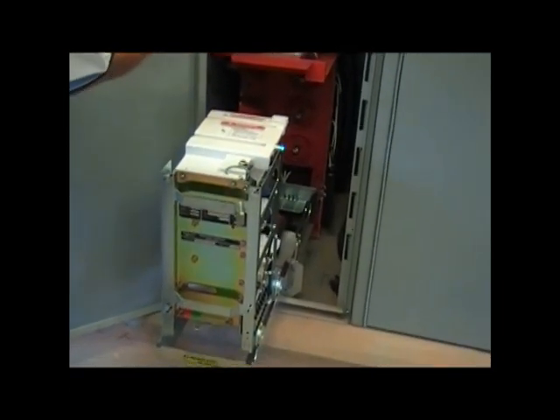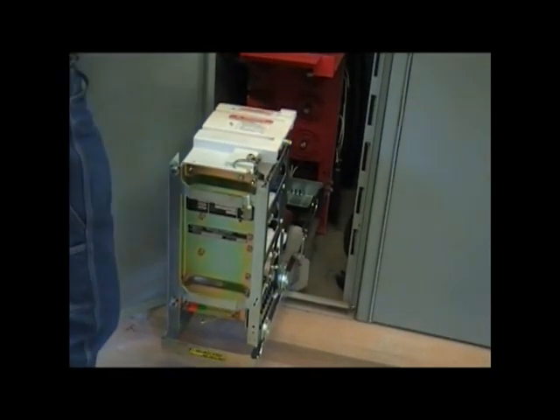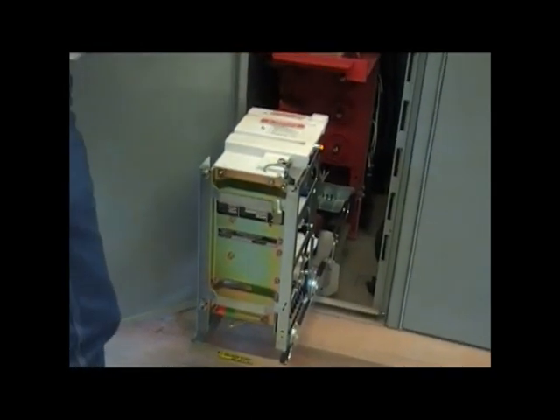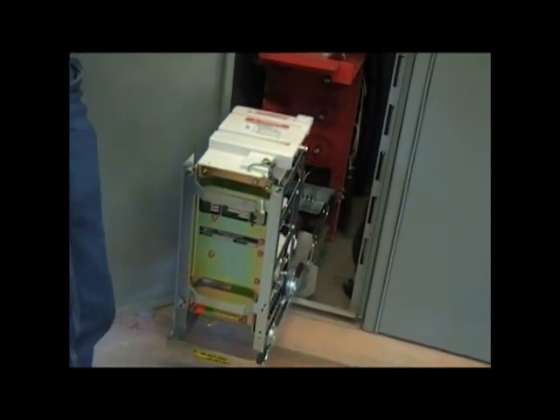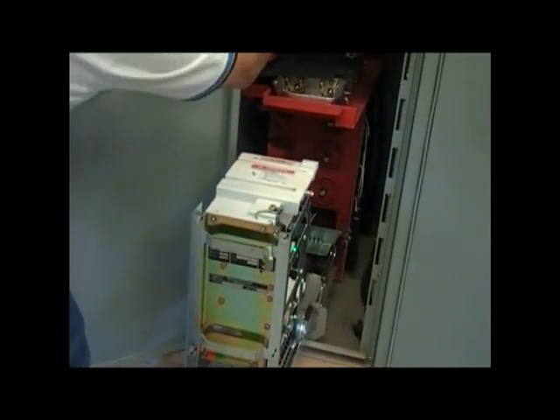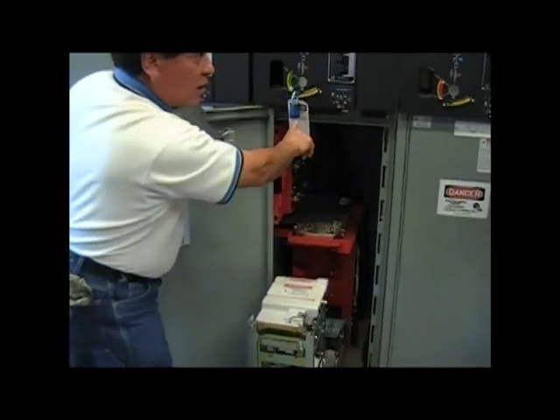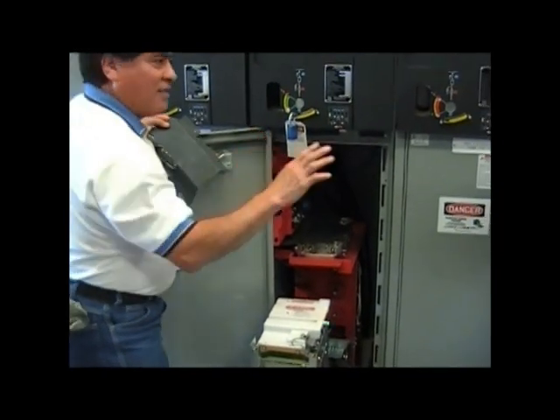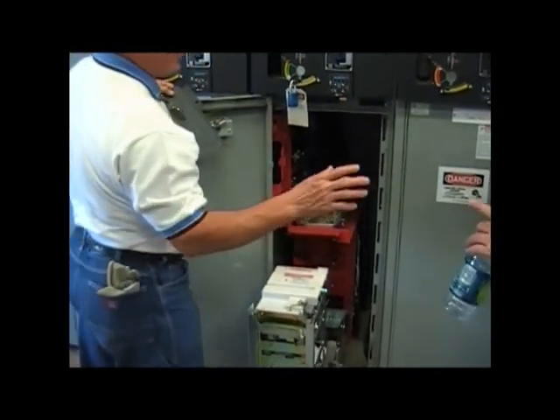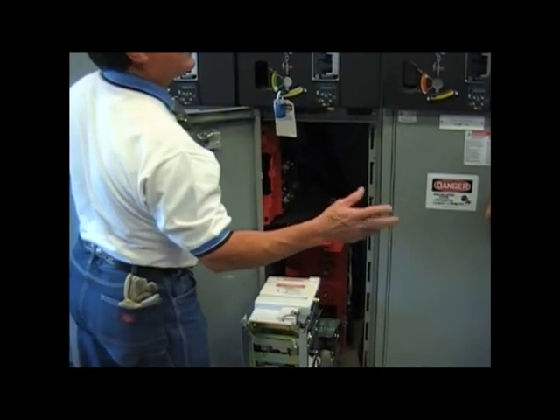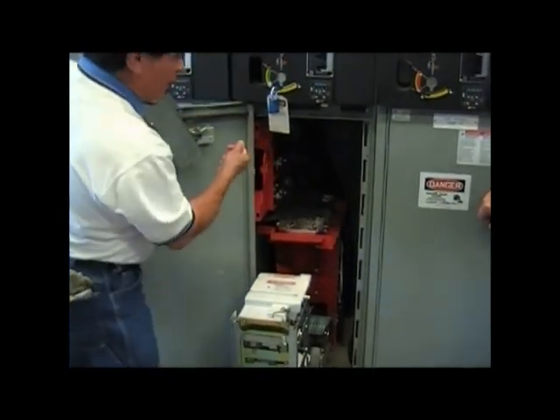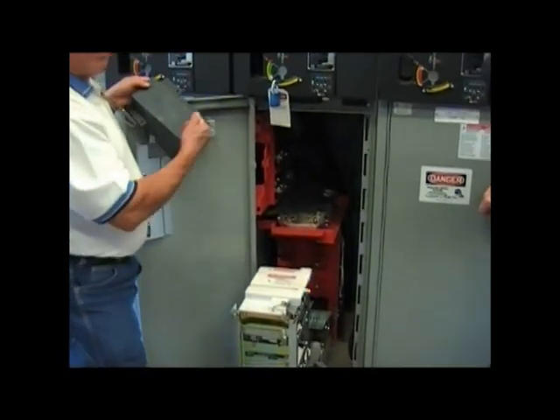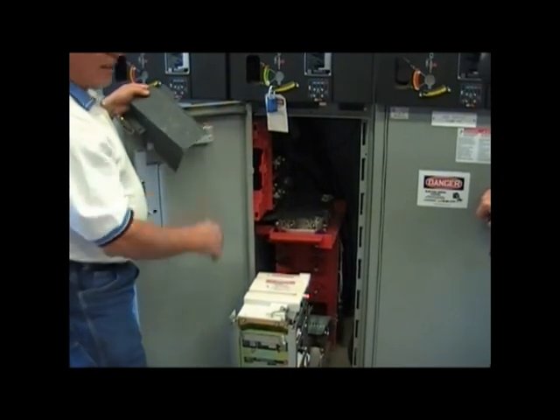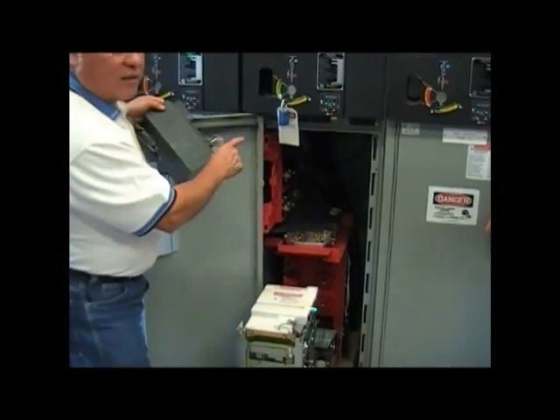The only thing you have to remember is that on the line side over here, because the switch is open - that disconnecting means is open - so those fuse clips on this side should not be hot. I said should not be hot, not are not hot. You heard me correct myself. So without a voltage sensing device or something like that, I'm not sticking my hand in there, because I don't know for a fact.